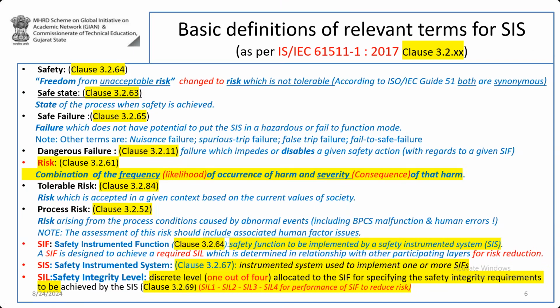Safe state needs to be elaborated a little. Our general understanding is that you shut down everything and it is safe. Now, shutting down everything is not the safe state as per the standard. The safe state of the process is when safety is achieved. That means in some processes, you cannot shut down. Can you shut down an aircraft if you find some fault in its safety system? If you shut it down, what will happen? It cannot ground safely. So you don't have to shut down everything, but there are recommended practices, and you have to define what is safe in case the automated safety system fails. If the automated safety system fails, then the pilot will manually fly it to a safe place to land. So this is what is to be defined as a safe state.